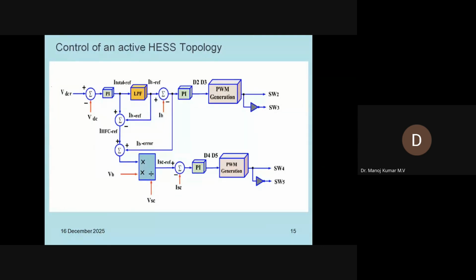Then this will be compared with the actual measured value of the voltage. So you require a voltage sensor to do the measurement of the actual DC link voltage, and the sensor's output will be compared with the reference value, and this will be given to a controller. It can be any type of control you go for.